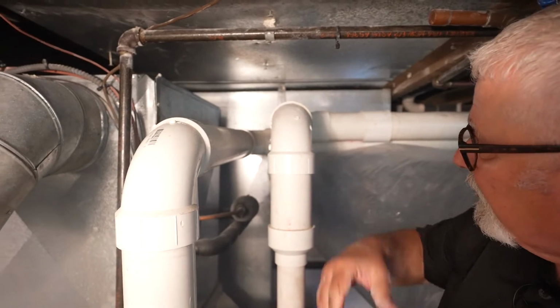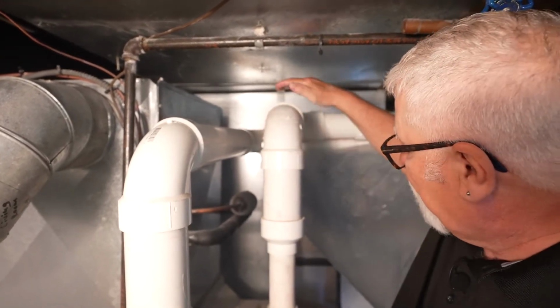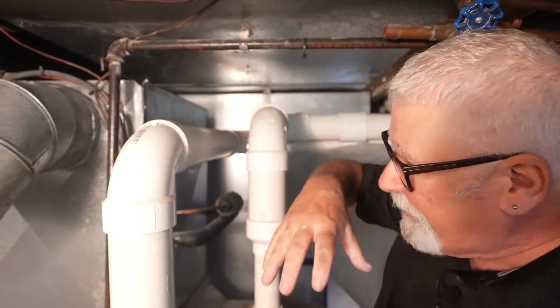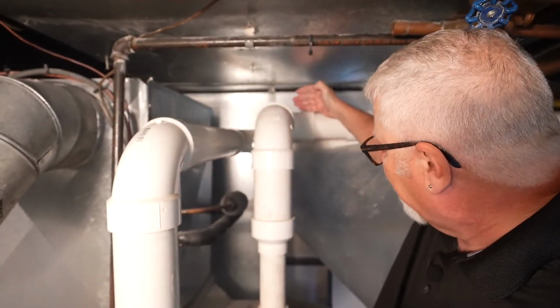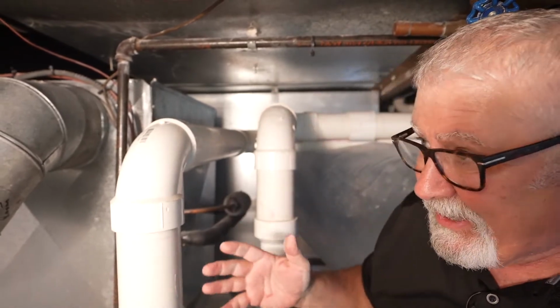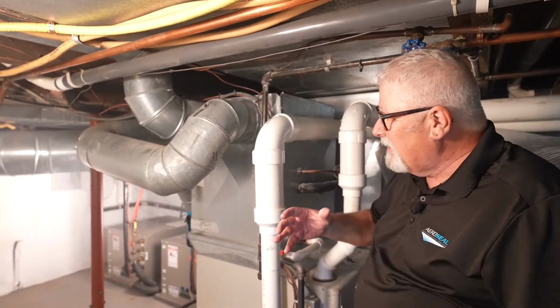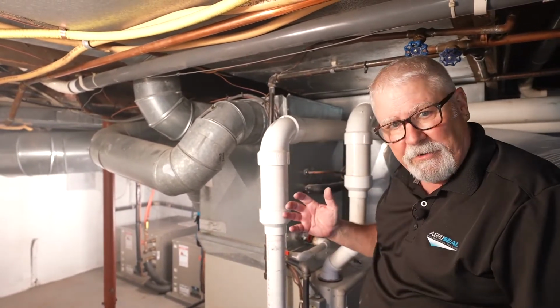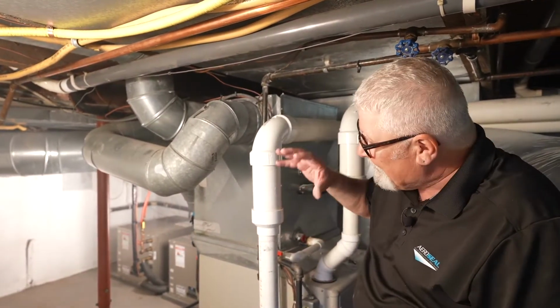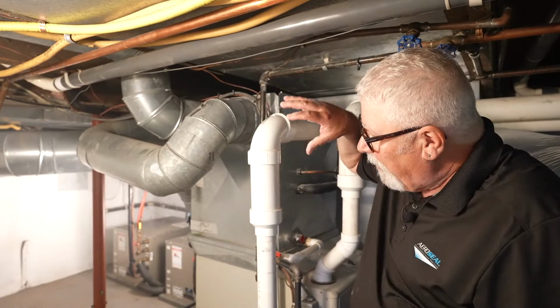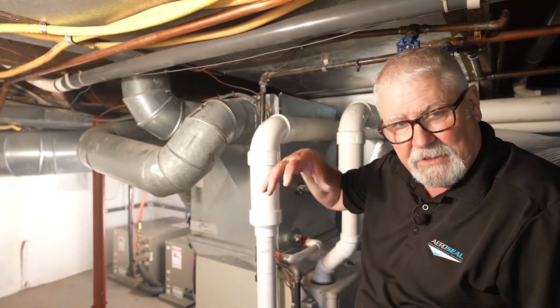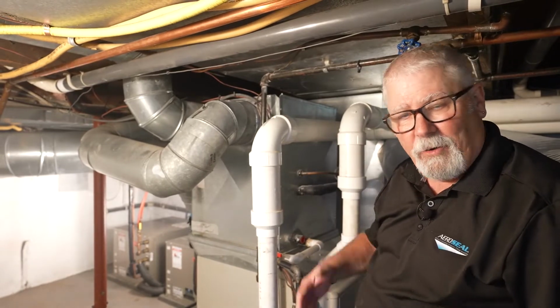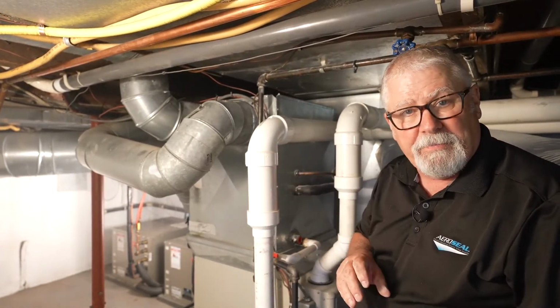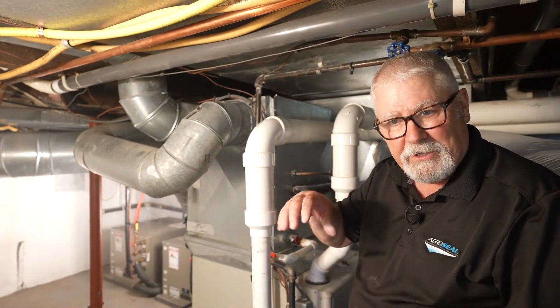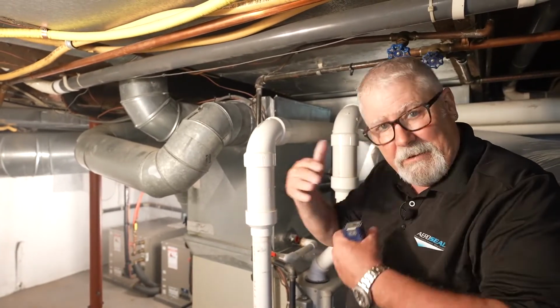The reason it's so important is because this is the return side. If I don't fix that and seal my supply ductwork, all the air from this basement gets sucked up into this hole and down into my return. We've got a dehumidifier down here for a reason, because this area is humid in the summertime, and all that humidity in the basement gets sucked into my return. It hurts my air conditioning, but as I get rid of my supply duct leakage, suddenly I've got real cold ductwork in a hot, humid basement, and everything's going to sweat. So I've got to stop this from happening. We talked earlier about that negative pressure - that's how it's created, air being pulled out of this space and going through my supply system.